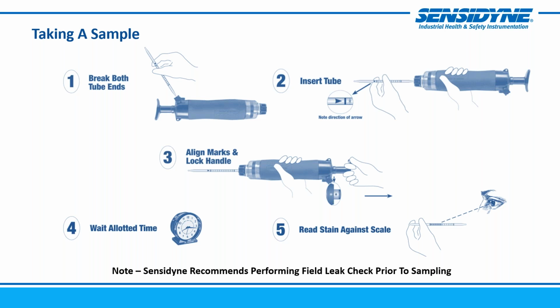I will note that Sensidyne recommends performing a field leak check prior to sampling. You pretty much follow these directions except for step one. You would leave the tube intact, insert the tube, align the handles, pull back the handle all the way to 100 milliliters, and this time you're going to wait 1 minute, and that indicator that I told you before will stay depressed. As long as that red indicator doesn't pop back up after a minute, you have a good seal and leak check performed. Then you can pull out the tube and start performing these steps.